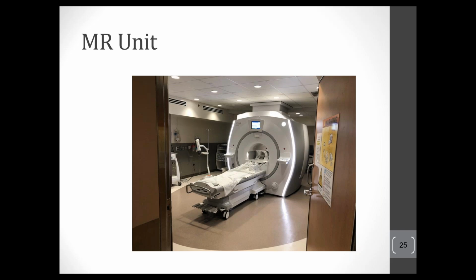One thing, there are actually a couple of hazards to keep in mind if you are looking at getting into an MR career or servicing them. You of course have the magnetism, so you can't have any kind of ferrous tools in there, at least you're not supposed to. Well, we won't discuss that one. So you don't want to go in the room with anything with a lot of metal on it, or any ferrous metal, I should say. The other thing that a lot of people don't keep in mind, and that same tech that caught me lounging on the floor in her MR suite, also would hand me a ball peen hammer made out of brass. And she goes, yeah, you need to carry this whenever you're in the room. And I was like, why do I need a hammer? And she said, okay, look at the door.